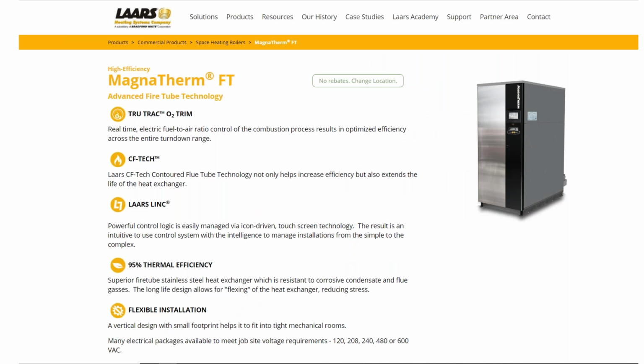So the Magnatherm FT, so everybody said, why don't you guys make a fire tube boiler? And Lars said, here you go. Here's your advanced fire tube technology. So once again, we didn't feel comfortable stepping into that place until we knew how to control it to the best efficiency. So this also has your TrueTrack trim, but we also have a CF tube technology, CF Tech, which is very good. It increases the efficiency and surface area and extends the life of the heat exchanger. LAARS LINC is also integrated here, and we have a 95% thermal efficiency. We have superior stainless steel heat exchanger in here as well. And once again, we have a smaller footprint. So let's take a look.